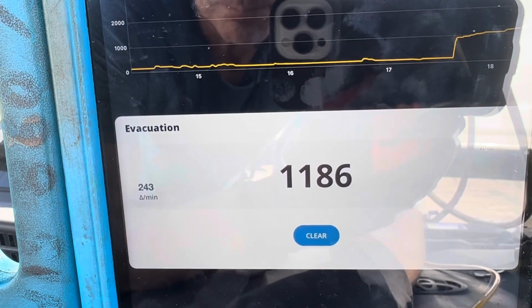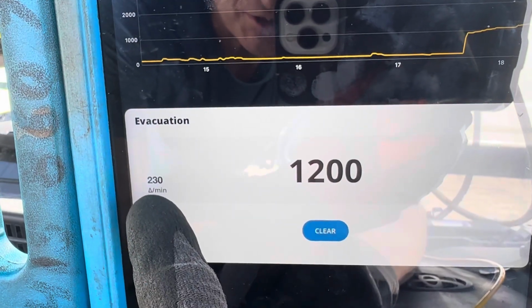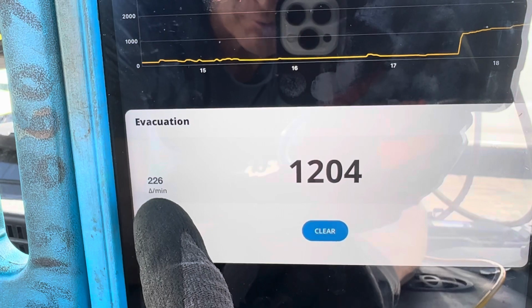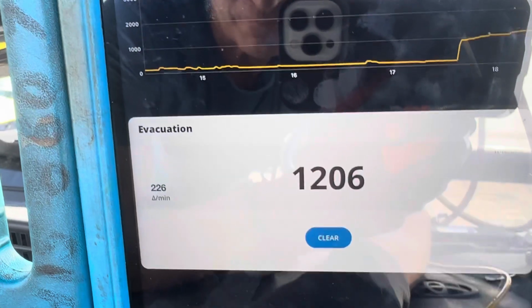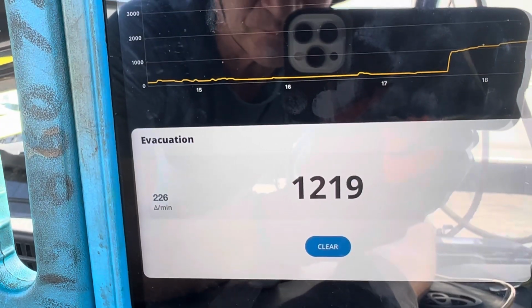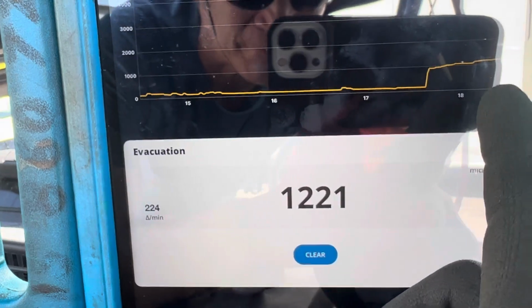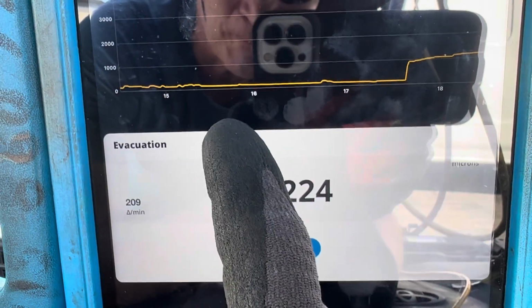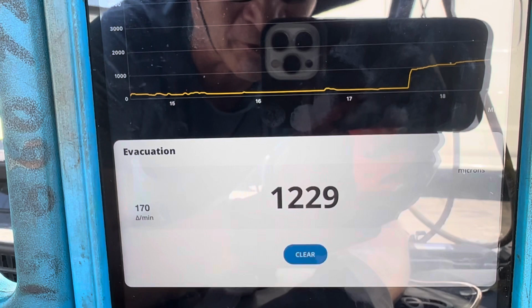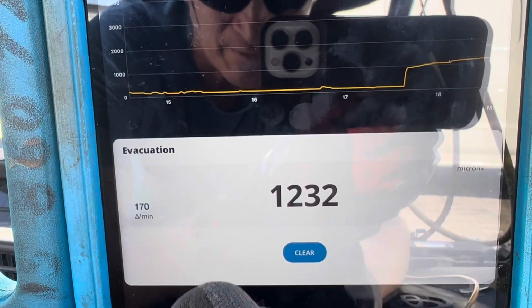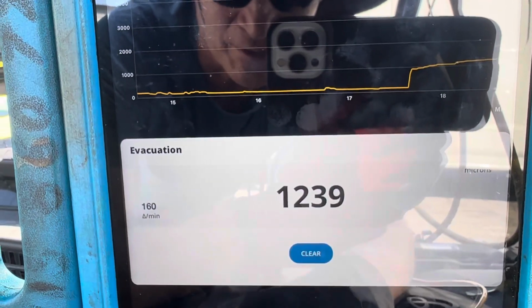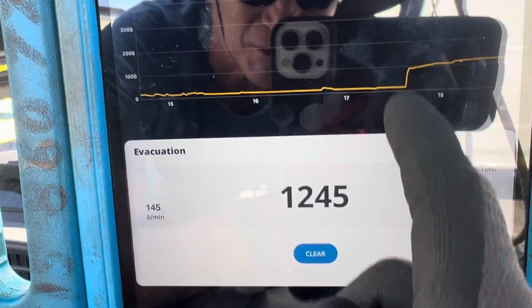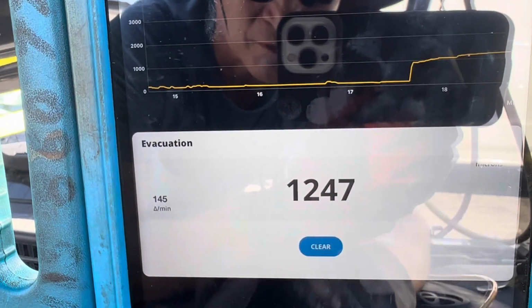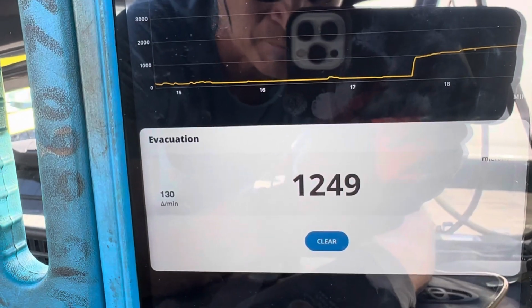As you can see, its estimation up here is pretty high on microns per minute. We're gonna go above 1,500 microns, but you see a drastic difference compared to before, when it was 3,400 microns. By throwing it on here additionally for 17 minutes, we almost made 18 additional minutes that I had it on the vacuum pump after we saw 6,000 microns.